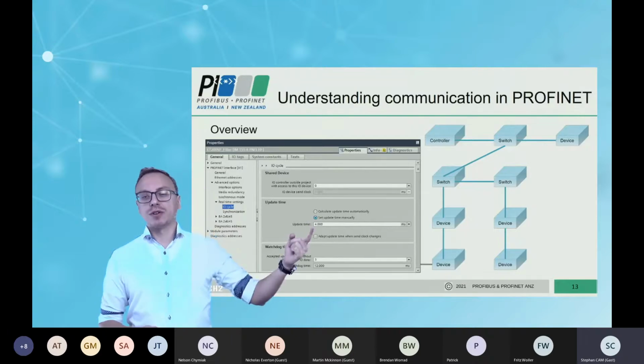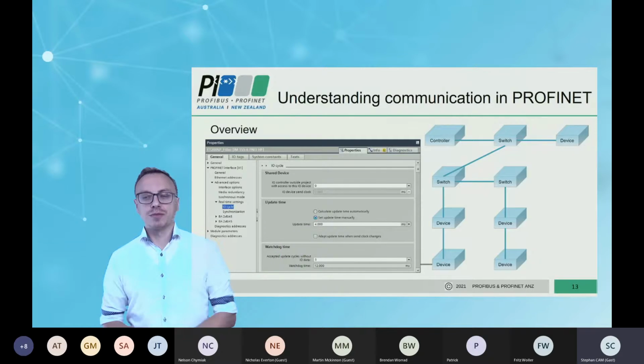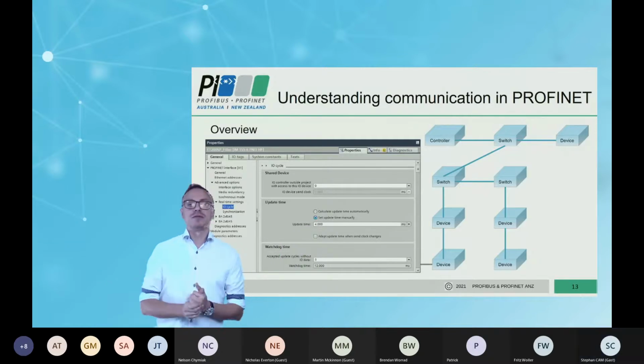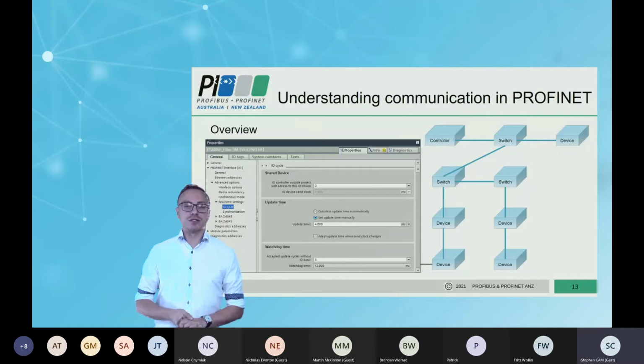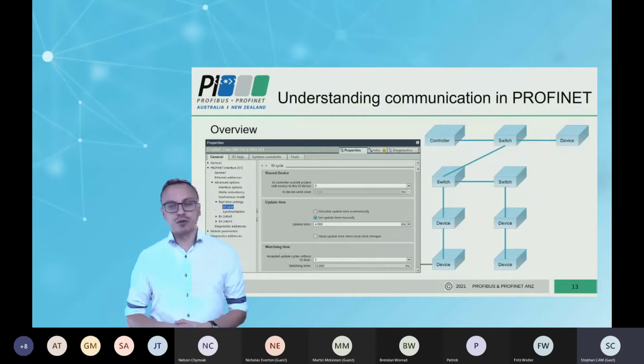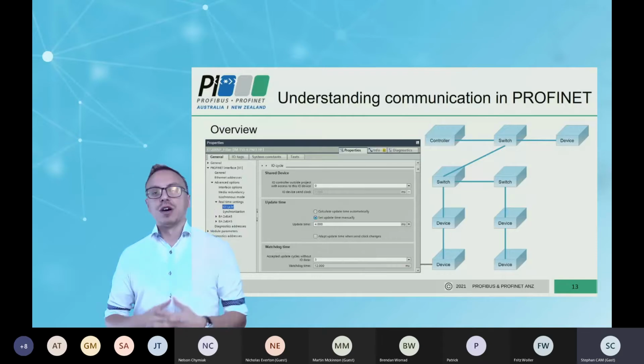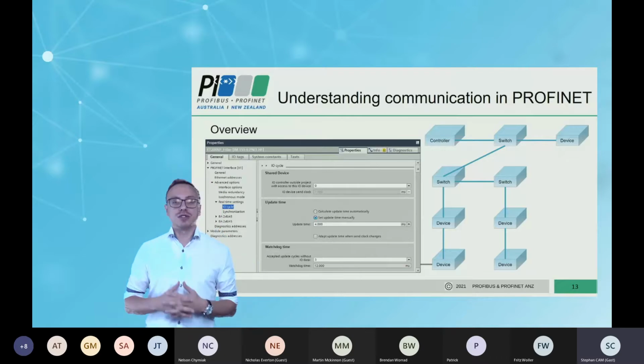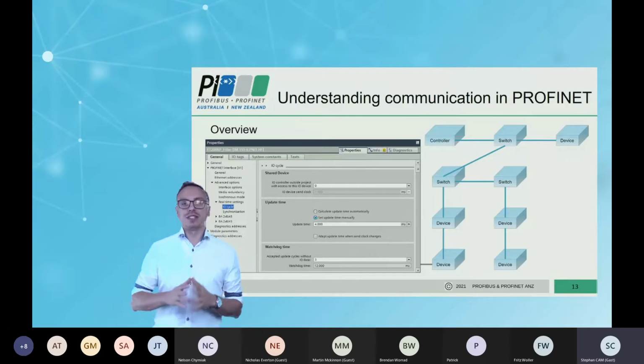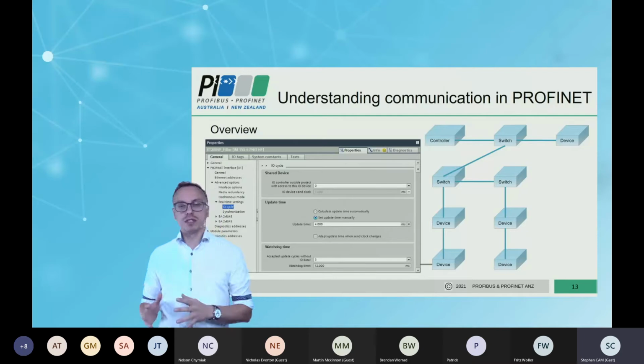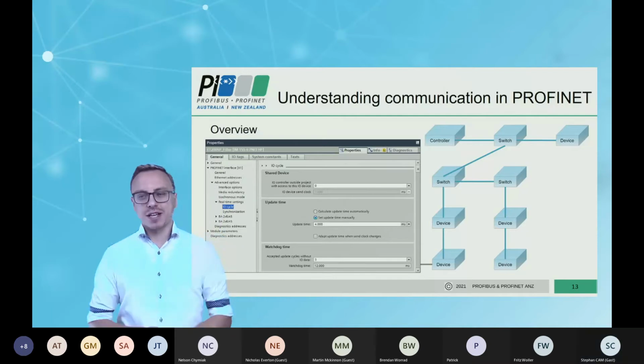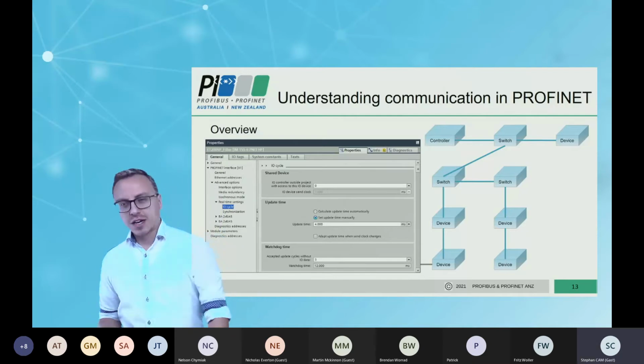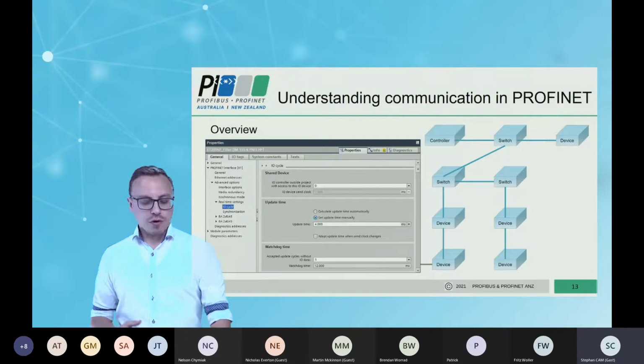Now you can change it, for example, to 8 milliseconds. And when you have a good situation for your process, that means you are twice as fast as your PLC. So if you have an issue, you still have protection, but your system has not so much traffic, and you will see in the next slide how important it is to have less traffic in your network. So this is only an overview of PROFINET.